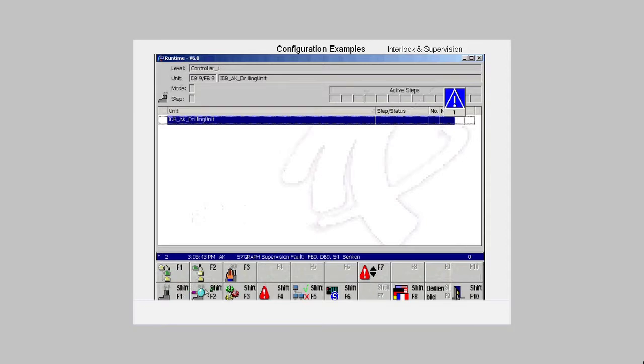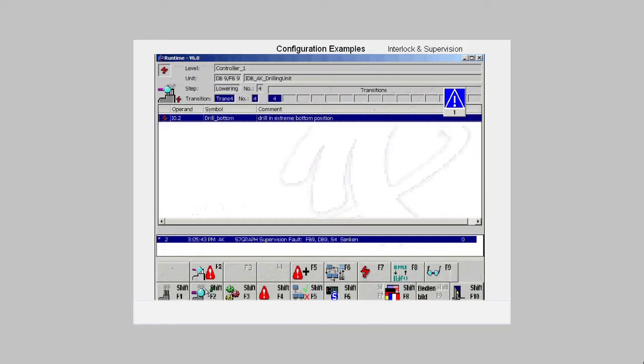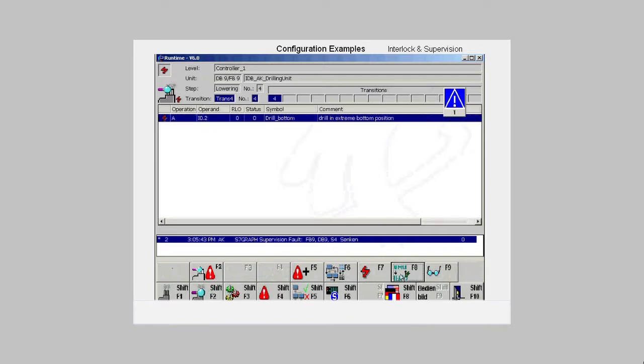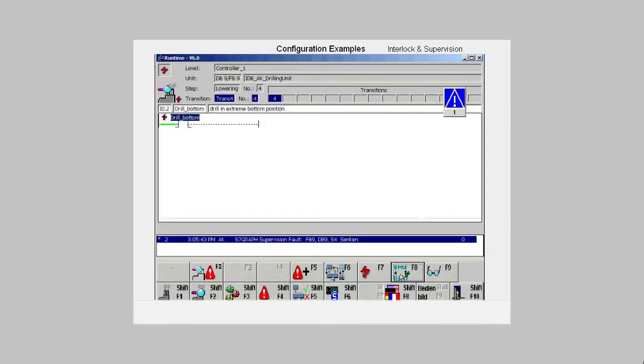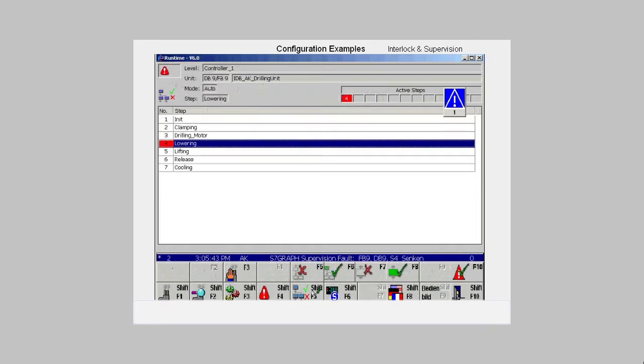In the detailed picture, you also get a display of the step, the transition and the faulty address. Now with the F8 button, we switch over to be able to see with which operation this address is linked. Another click on F8 shows us the address in the ladder view. With Shift F5, we switch to the sequencer view in which the number of the blocked step is marked red.